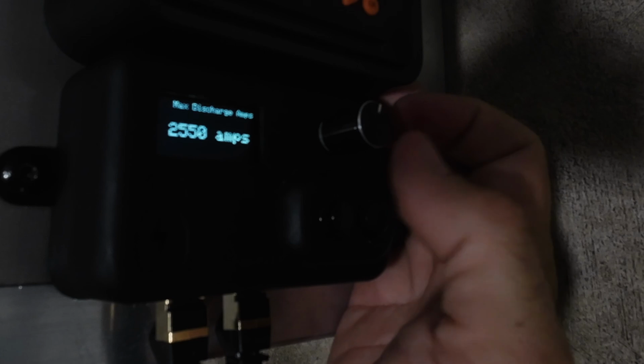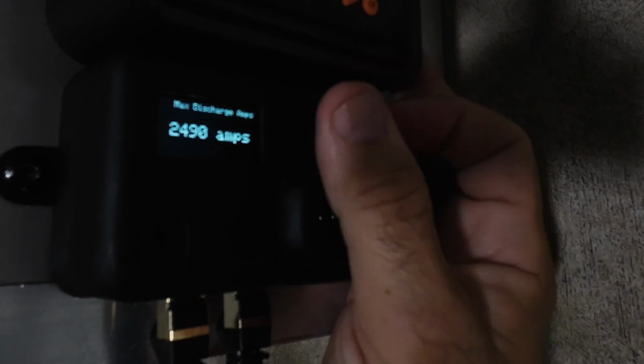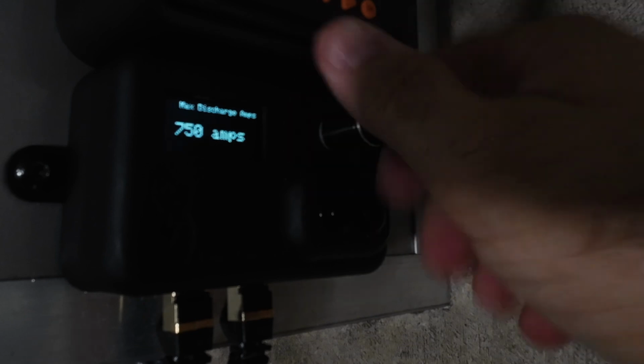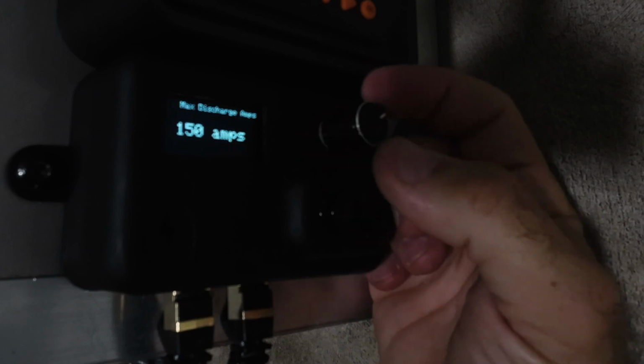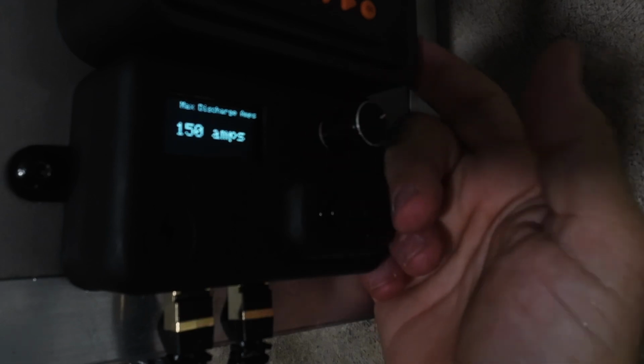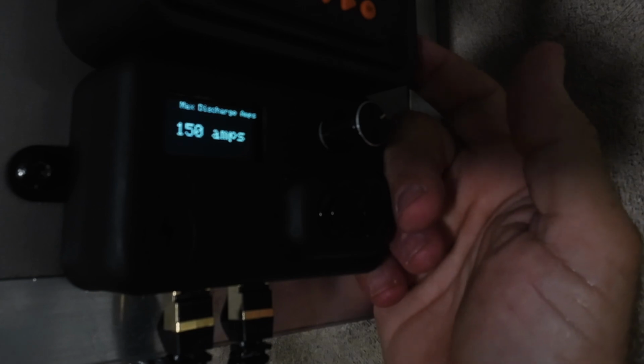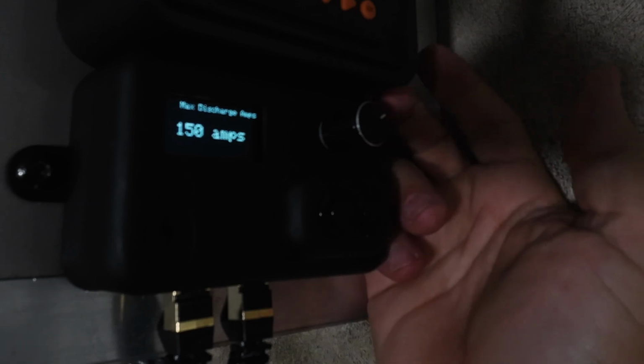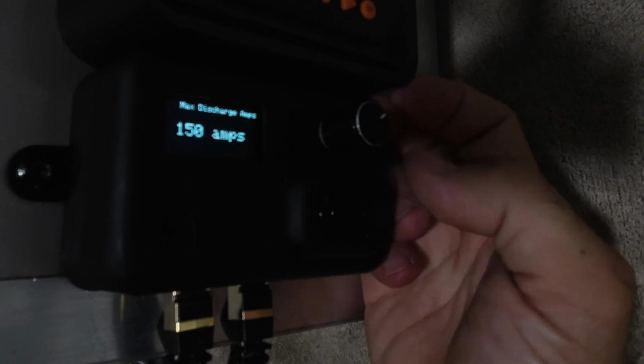Max amps, this is kind of like a fuse, and you can lower this number down. Like I'll set it for, oh geez, there's no reason in this installation I should ever go over 150 amps of draw. And if I do, something's wrong, like there's a short circuit. So this kind of becomes a software fuse. Never trust software to do fusing. But if you have a fuse, and let's say you have a 200 amp fuse, and you set this for 150 amps, this will likely protect your real fuse that costs money, and this is just software, so you can just reset it once you fix the problem.